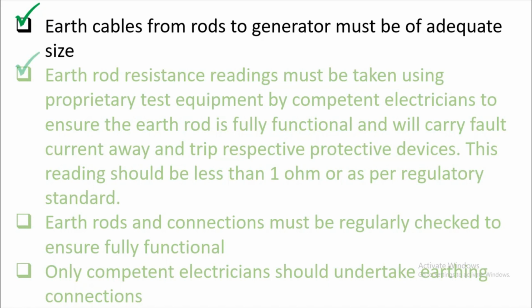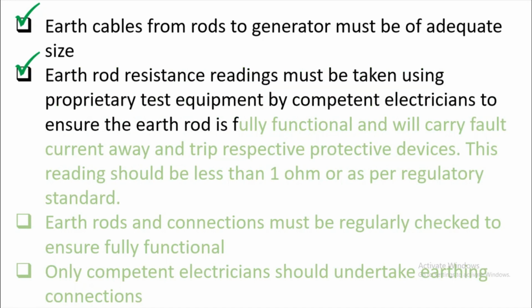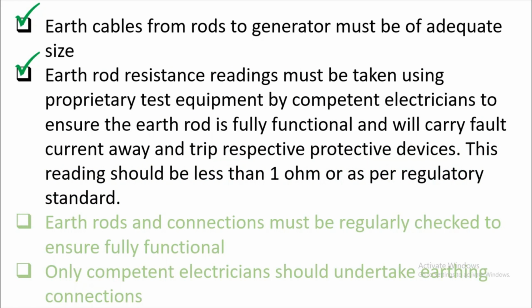Earth rod resistance readings must be taken using proprietary test equipment by competent electricians to ensure that the earth rod is fully functional and will carry fault current away and trip the respective protective devices. This reading should be less than 1 ohm or as per the regulatory standards of your locality. Okay? If there are no standards in your locality, then it should be less than 1 ohm. So your electrician will test all the connections of the earth rods.